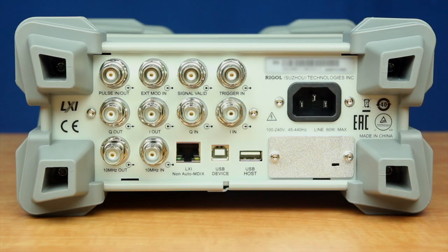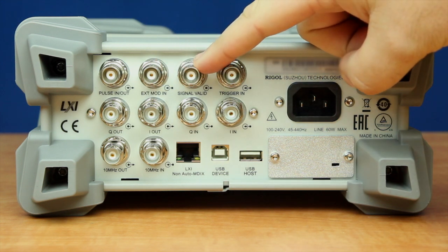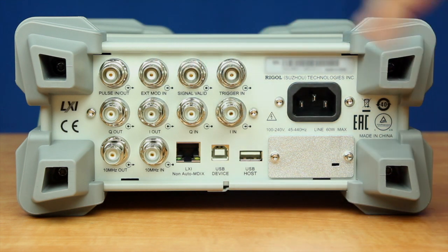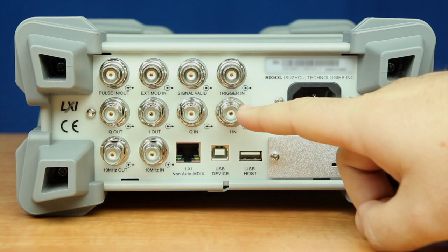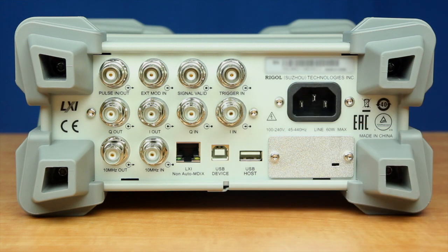On the back panel of the instrument we have several BNC connectors which allow the instrument to interact with other instruments. For instance, we have a pulse in and out, then external modulation in, a signal valid out, and then a trigger in. For the DSG-800A models we have a Q-out, an I-out, and then Q-in and I-in, which allows other instruments to create IQ data going into the instrument.